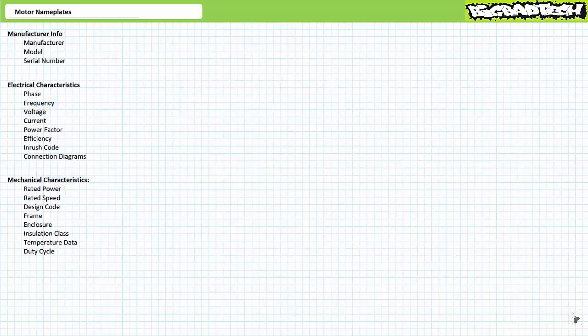A motor nameplate is a mini data sheet affixed to a motor in question describing its most important characteristics at the rated condition. In the event a motor is damaged, one can order an exact replacement or, lacking an exact match, interpret the motor nameplate entries to find a comparable replacement from a different manufacturer. In a perfect world, all manufacturers would utilize a common template, thereby enabling readability and interchangeability, but they don't, and it is the wild, wild west, and absolutely anything and everything goes. This being said, most manufacturers have enough sense to include the most important information, even though it might or might not appear in the same location.